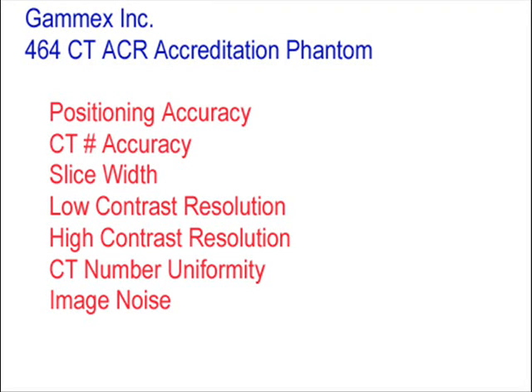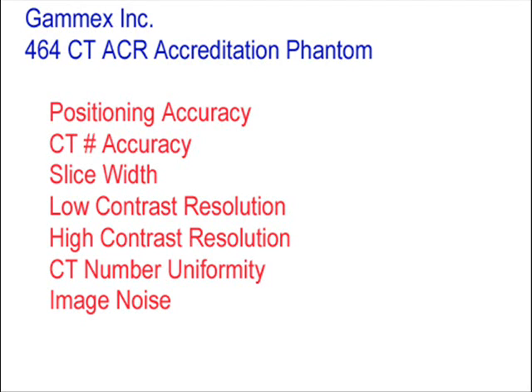The Gammex ACR CT Accreditation Phantom has been designed to examine a broad range of scanner parameters, including positioning accuracy, CT number accuracy, slice width, low contrast resolution, high contrast resolution, CT number uniformity, and image noise.